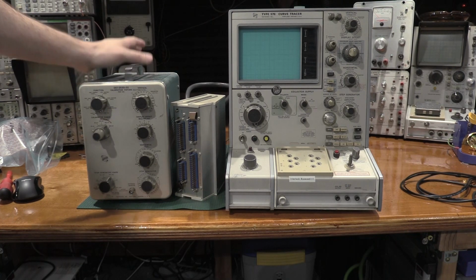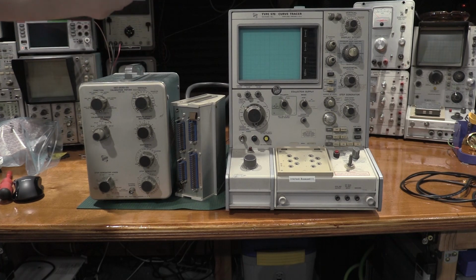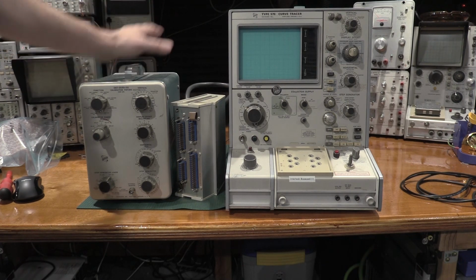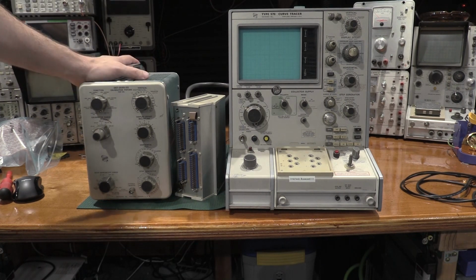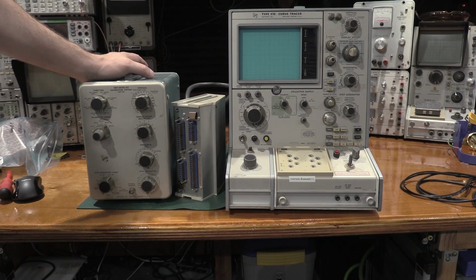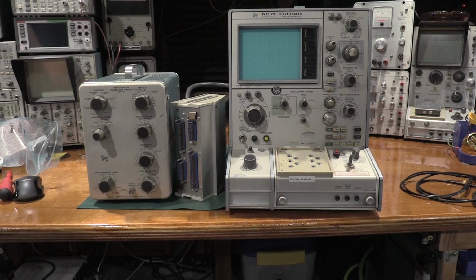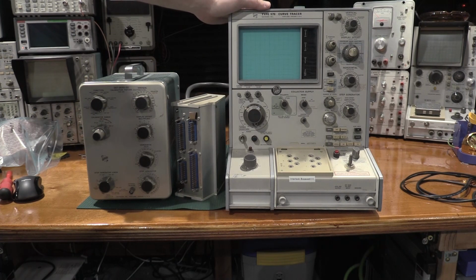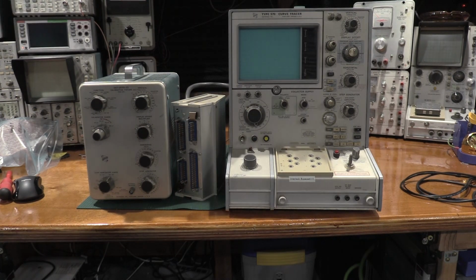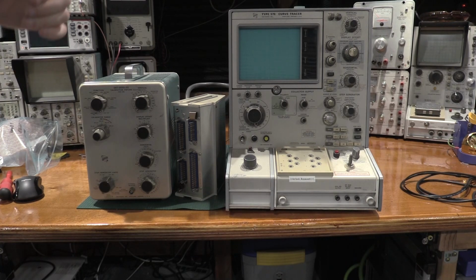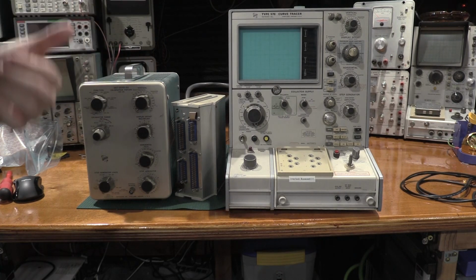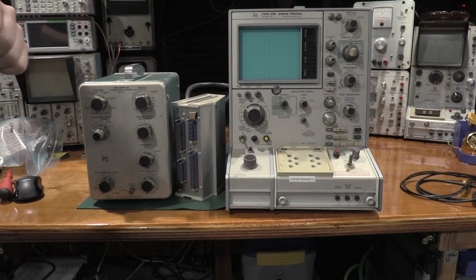they sent it to me. So I actually got a calibration report on this. This was not inexpensive when I purchased it, but it did get these units up off the ground and gave me confidence in their measurements. The other thing is this can put out some decent amount of power. So not only do you need very high voltage components to do the calibration, you also need some decent sized power resistors to do the calibration and alignment.